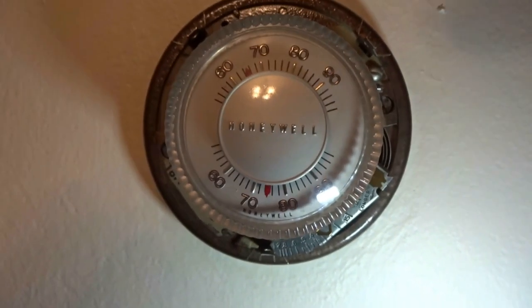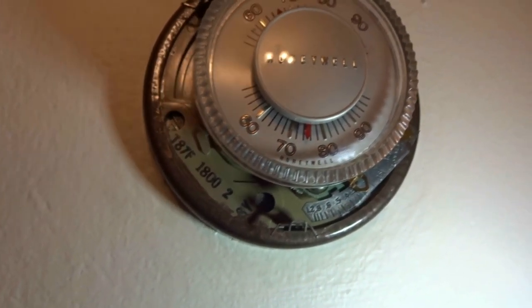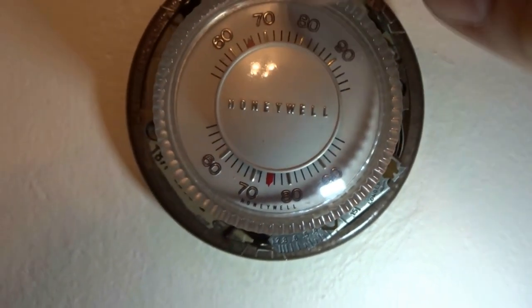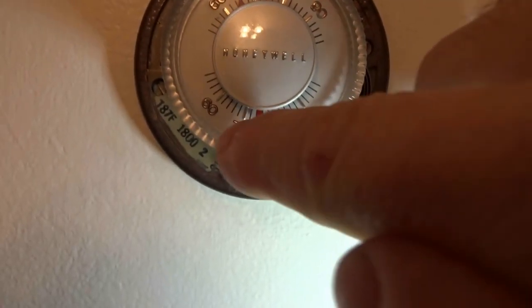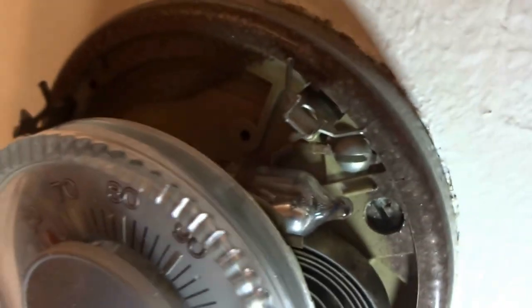Today I had a chance to take this off — it's a Honeywell T87F 1800 2. Up here you've got your numbers; this is your setting, I've got it set at 64.5. Down here it's reading 74 degrees. This is the old mercury type and I prefer these.